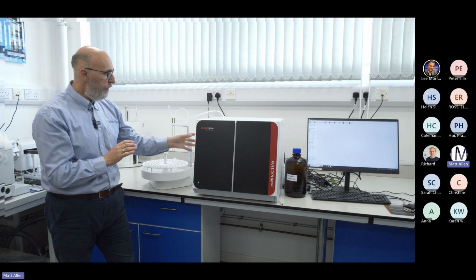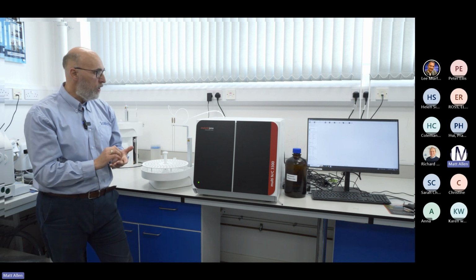People will use that normally if they need that working range, that lower LOD, or typically they're following a method that states you must use a chemiluminescence detector. But those are the detectors, the focused NDIR for the carbon, and the two options with the nitrogen. Now, it's worth pointing out that the carbon detector and the furnace are so robust, so well made. They both have extended warranties. They come with, as standard, 5-year warranties. So very, very well made and designed.